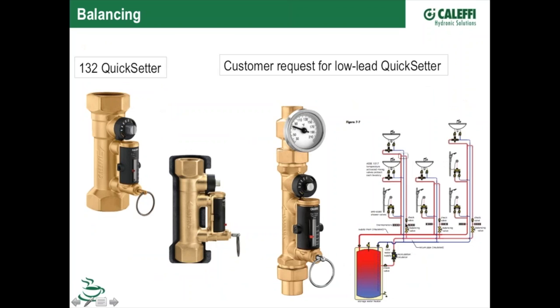If I don't know a flow rate, I don't have the design criteria, I could just use the temperature gauge on that, because really all I want to do with that recirc is overcome the temperature drop going through this piping circuit here. So if I'm going out at, let's say, 120 degrees out of the tank, I want to have about a 10-degree temperature drop, make sure that the last fixture on the line gets a reasonable temperature. I can just adjust that by the temperature gauge. So it's really nice for that.